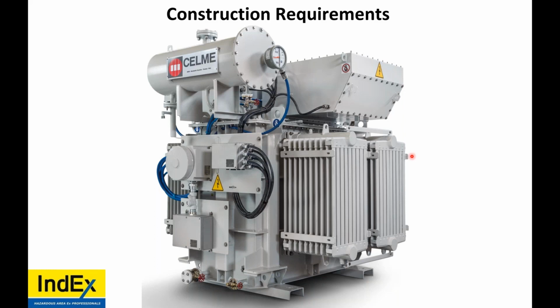Now, when we look at this, here's your terminal enclosure. Here's your oil compartment reservoir. Then you have Ex e terminal boxes, and then you have an Ex d. And you also have intrinsically safe cabling going to other locations on this piece of equipment. So what does that all mean?